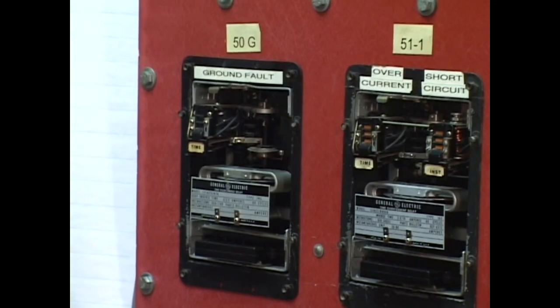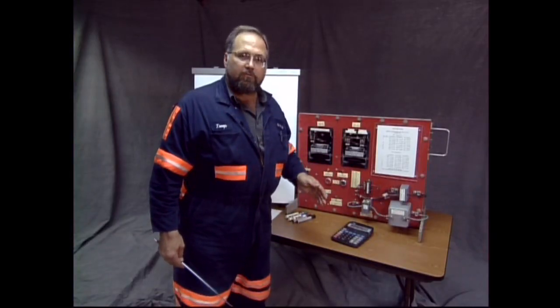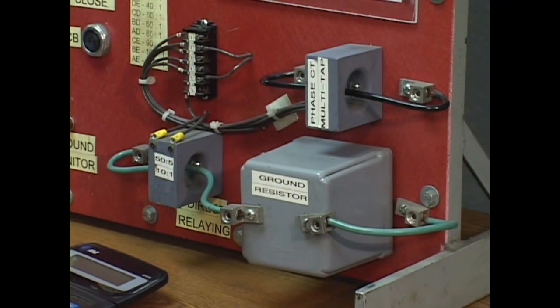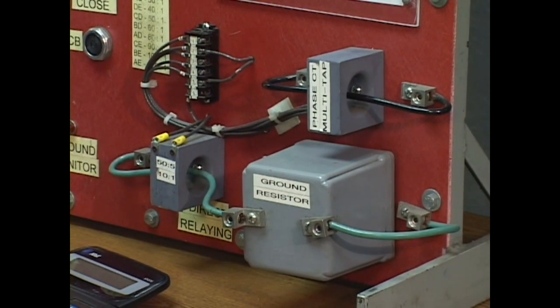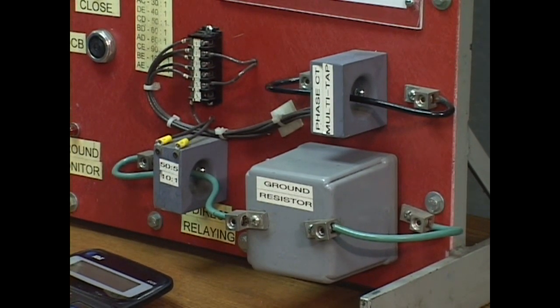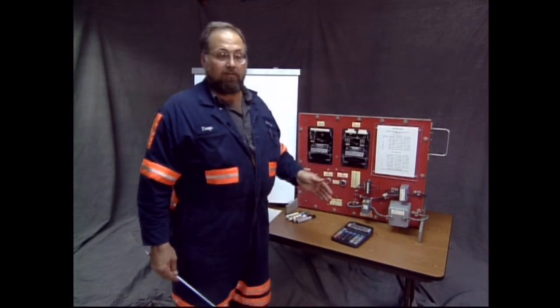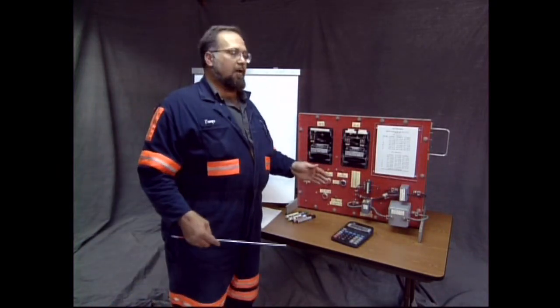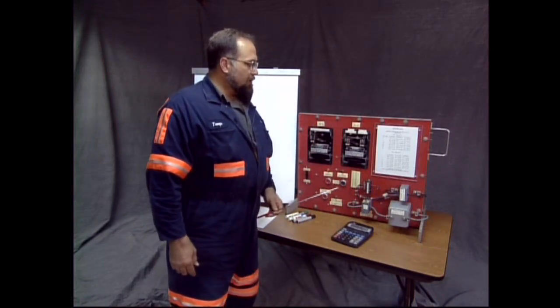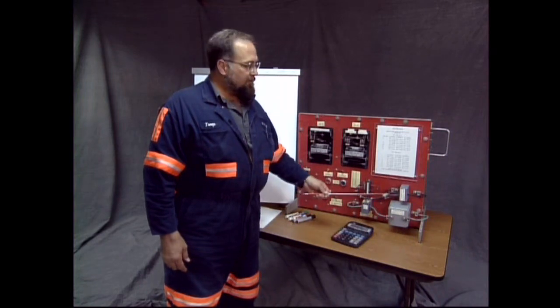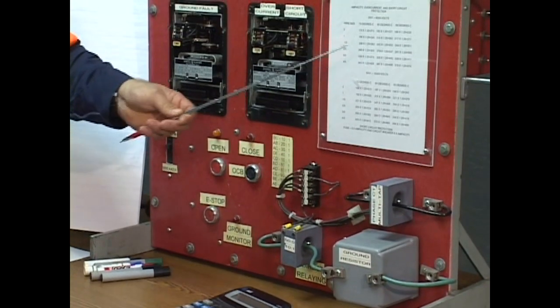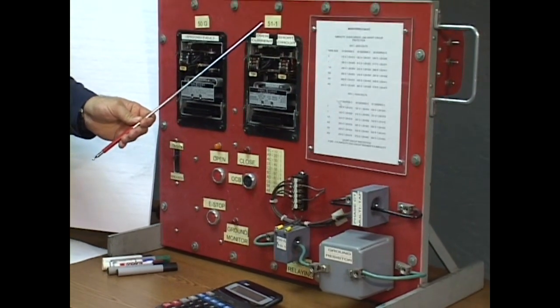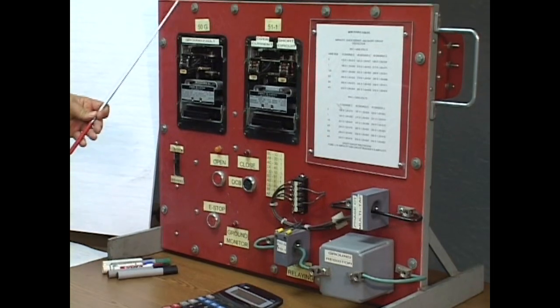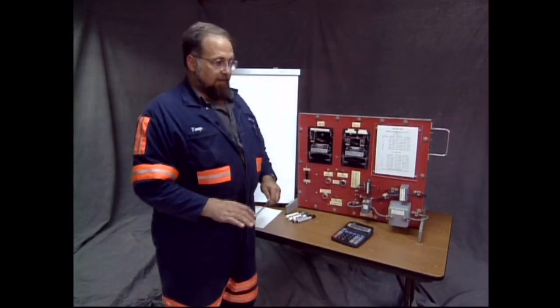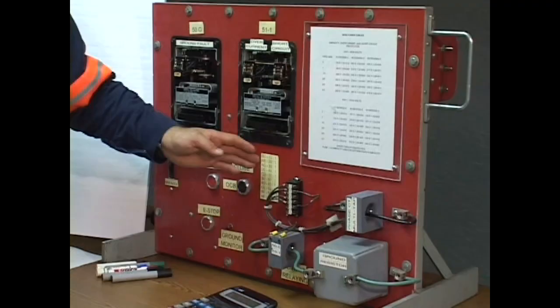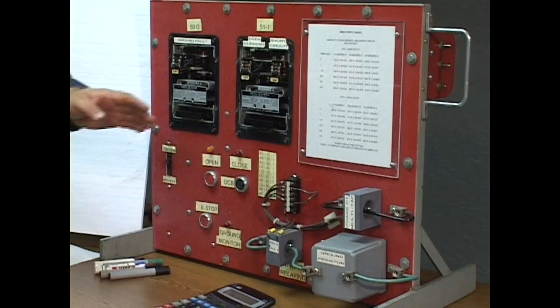What determines its ampacities, how high you can set it, is the rating of the ground resistor. The ground resistor is rated for a continuous duty cycle, 100%, 24/7. It's rated to deal with 25 amps continuously. Now, as a redundancy, we're not going to challenge that ground resistor. By law, you're allowed to adjust the 50G to not exceed 50% of the ampacity of the ground resistor. Ampacity of the cable dictates setting the time overcurrent relay for phases. The ampacity of the ground resistor settles the setting for the ground fault relay. Okay, so you'll note all of these different ratios here. They're to accommodate the various settings for the cable.